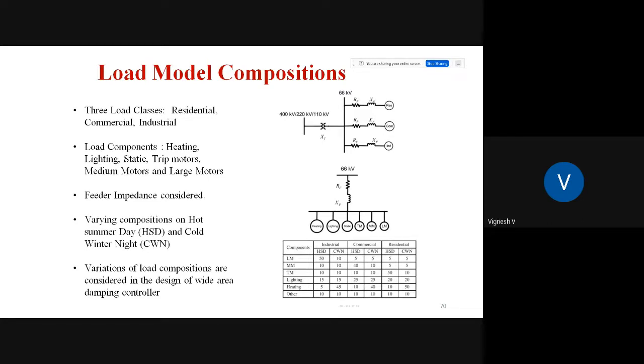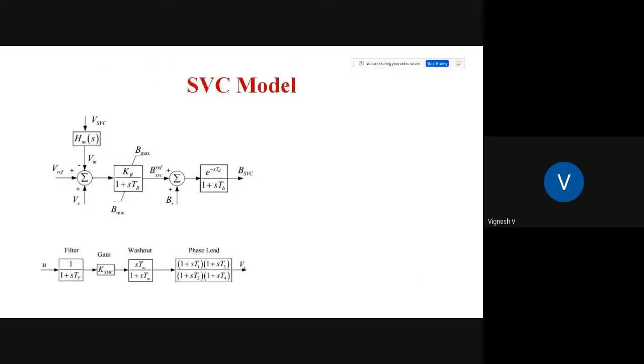We have also modeled the SVC in this case. The SVC model is from the standard literature. For this SVC model, we added an additional damping controller, shown in the bottom block diagram. VS is the supplementary voltage signal to damp out the interarea modes of oscillation. We use a phase lead compensator for the damping control of the SVC.